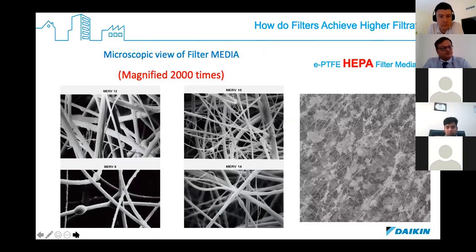Next slide, please. So we go with filtration, right? MERV 14 is the filtration efficiency that was recommended to operate. I've just put a microscopic view of it. So what actually happens: if you have MERV 8 filters, you can see the amount of space wherein dust particles cannot be arrested. But as you move on to 12, to 14, to 16, your arrestance of dust particles is much higher.